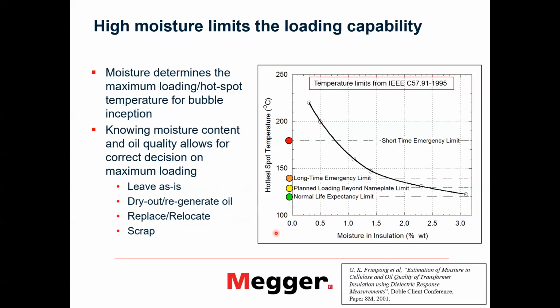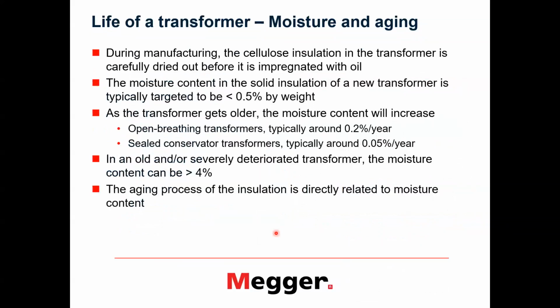And if we know the moisture content and oil quality, we can also make a decision what to do with the transformer, whether it is okay to leave it as it is, even if it is more wet than we would like. We can dry it out or regenerate the oil. We can, of course, replace it and put the transformer into less critical places in the network, or simply scrap it and put in a new transformer, which is actually the last thing to do.